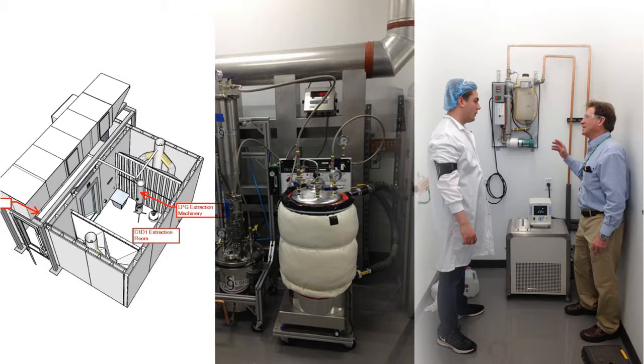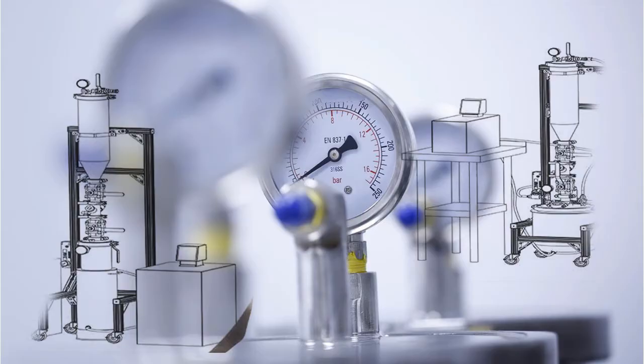In addition to the dedicated ventilation, you'll have a dedicated fixed monitor for flammable vapors or gases that's operating continuously. That detector will be connected to an alarm, both an auditory alarm and a visual alarm. So if by chance there is a gas release and it exceeds 25% of the lower explosive limit, the operator will be informed by the alarm and then instructed to follow the SOP, which essentially means secure the equipment, turn off everything, leave the room, and let the ventilation do what it's designed to do, and that is reduce the concentration of airborne explosive gas.